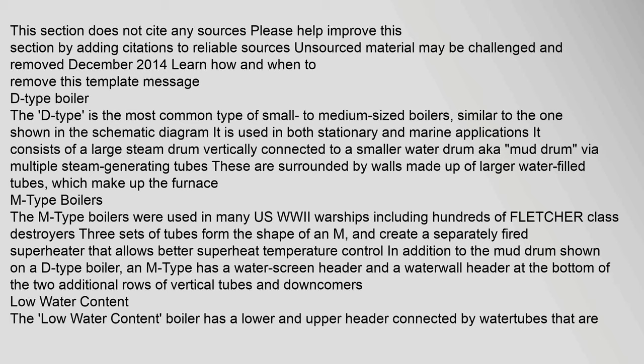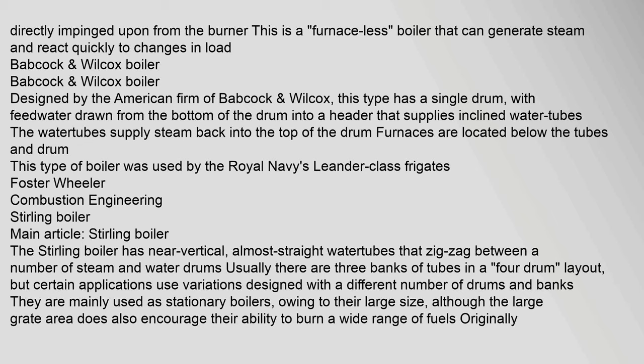The M-type boilers were used in many U.S. World War II warships, including hundreds of Fletcher class destroyers. Three sets of tubes form the shape of an M and create a separately fired superheater that allows better superheat temperature control. In addition to the mud drum shown on a D-type boiler, an M-type has a water screen header and a waterwall header at the bottom of the two additional rows of vertical tubes and downcomers. The low water content boiler has a lower and upper header connected by water tubes directly impinged upon from the burner, and can generate steam and react quickly to changes in load.